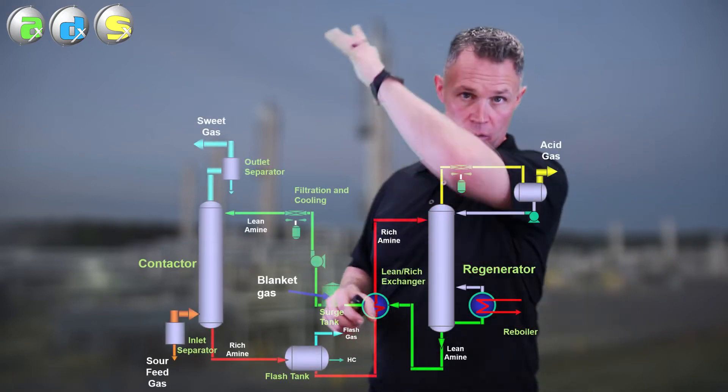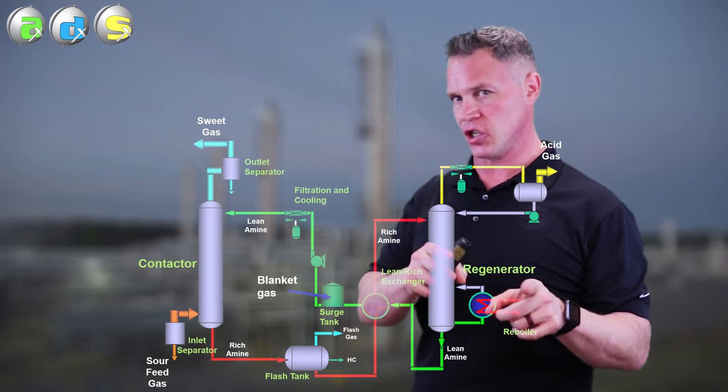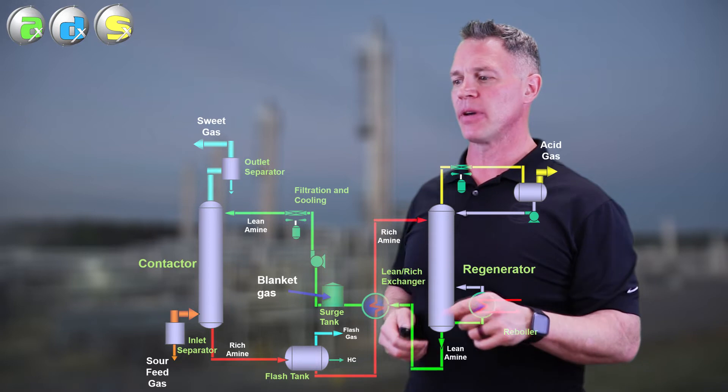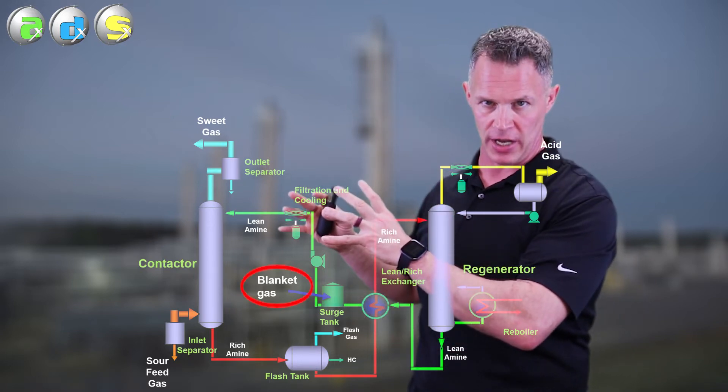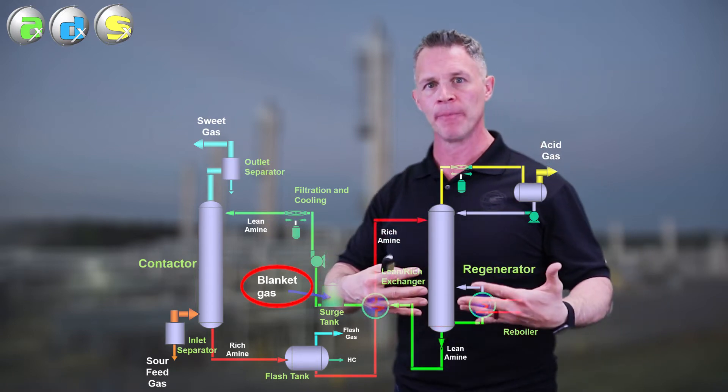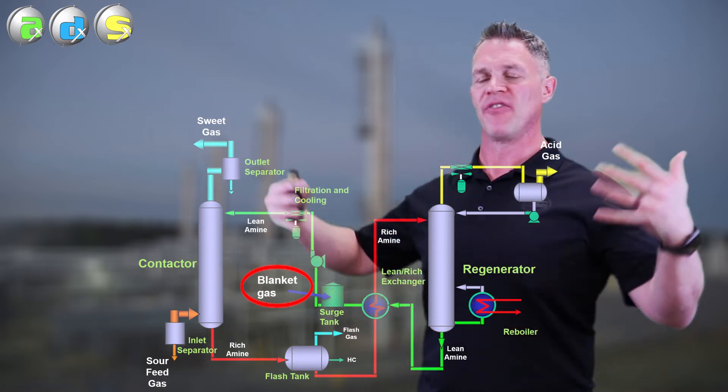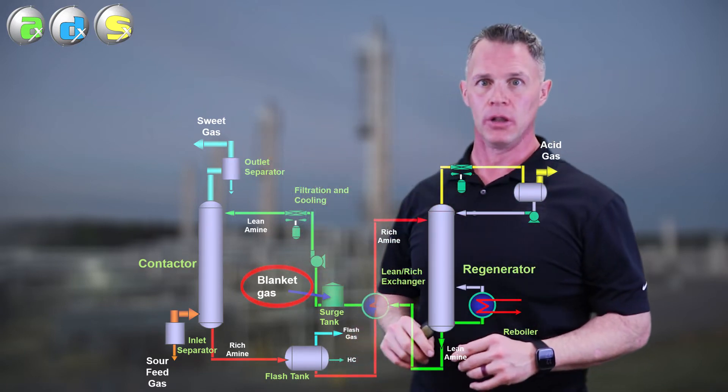Oxygen normally comes from two sources. Either it's entering with your feed gas and going right into your amine absorber, or if you have a surge tank, it can be coming in from there as well. It's why we keep blanket gas on our surge tanks, usually nitrogen or fuel gas, some type of inert gas that will prevent air from getting into the surge tank when the amine level lowers.